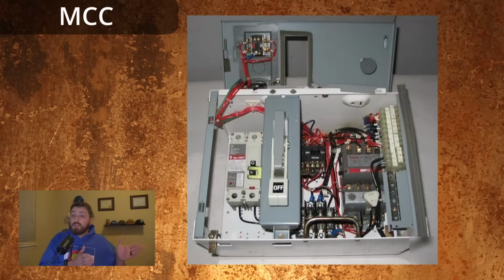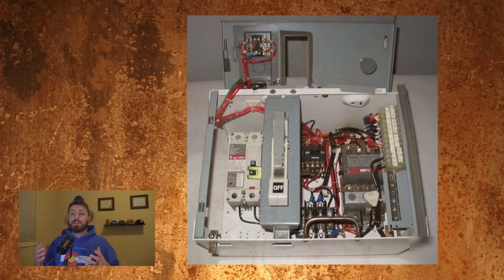Now, in a switchgear, you can rack out one large breaker from its cell. In an MCC, you can yank the entire bucket, the entire enclosure, including the breaker and control components, right off of the bus. Let's get back to why these names are important and why you should know the difference. Primarily because you don't want to sound stupid in front of your customers and coworkers. Secondary to that is safety.